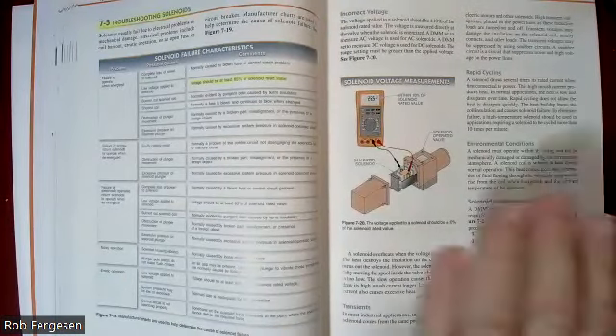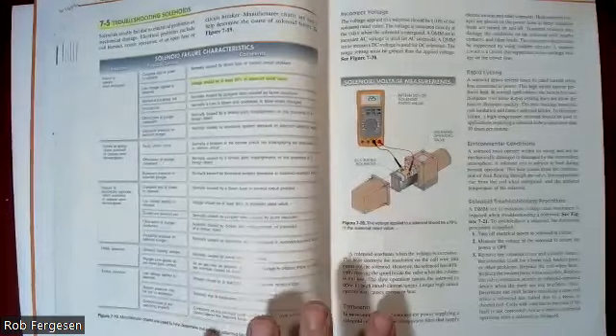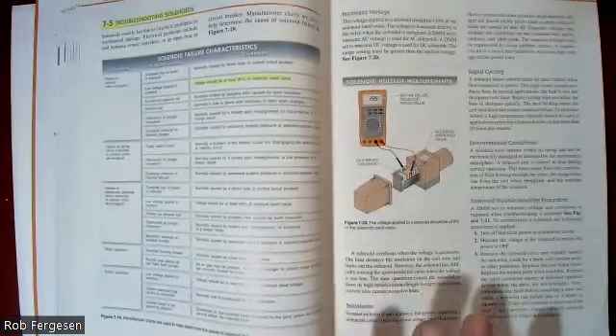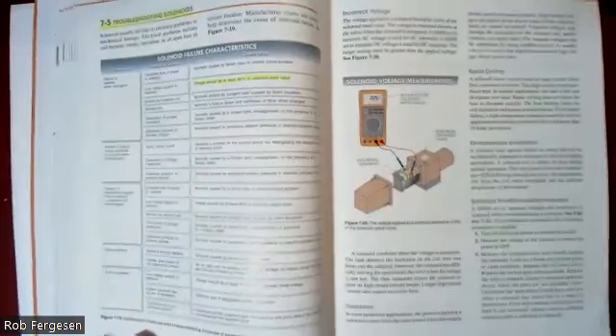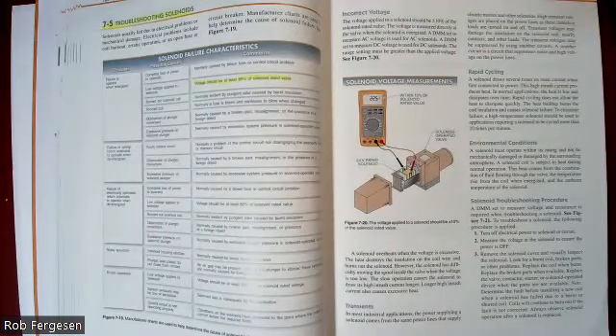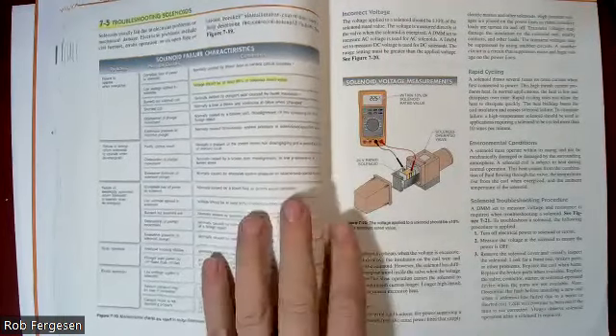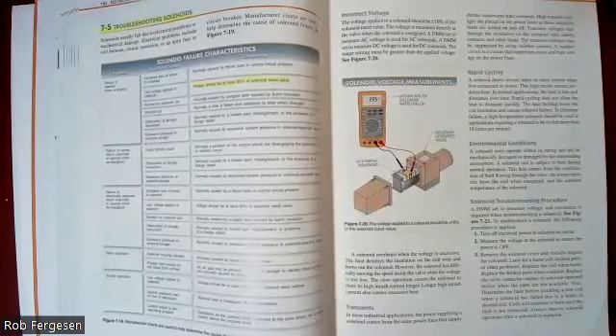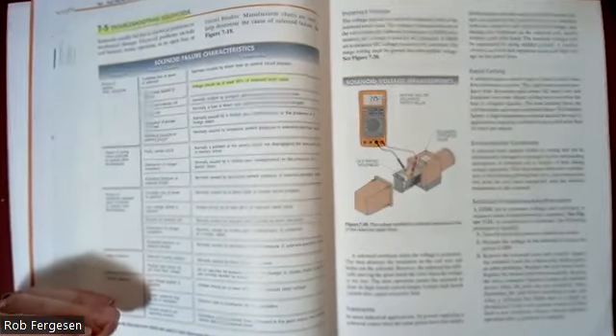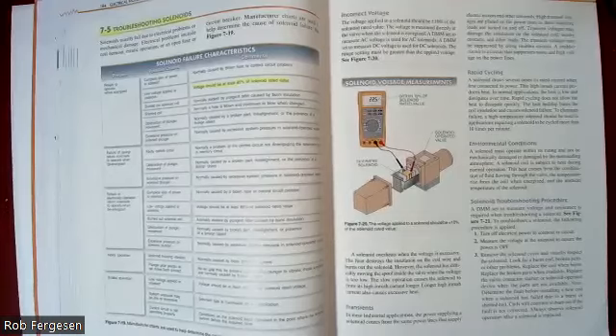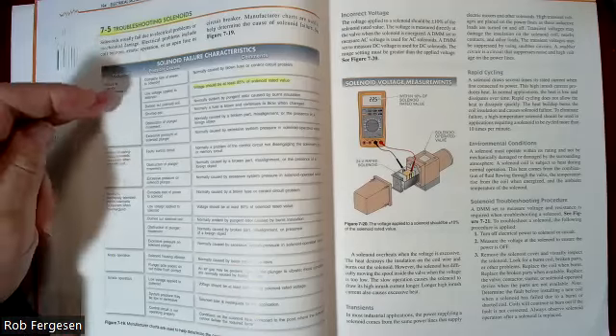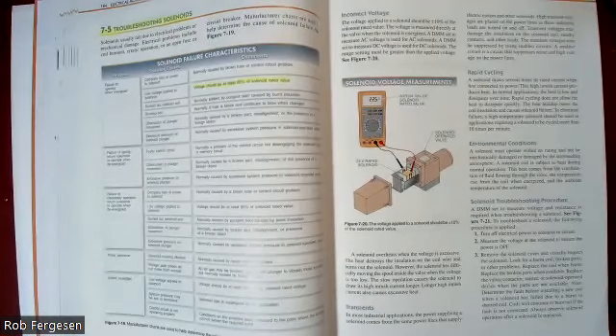Troubleshooting solenoids. Guys, if there's one reason to keep this book and not rent it, it's these troubleshooting tables, right? So you may want to just copy out these tables, even if you're renting your book, and keep them in a binder, because they're very useful to help you organize your troubleshooting steps anytime you've got a problem with the solenoid valve or a relay or a contactor. It just steps you through the possible failure modes and how to fix them.